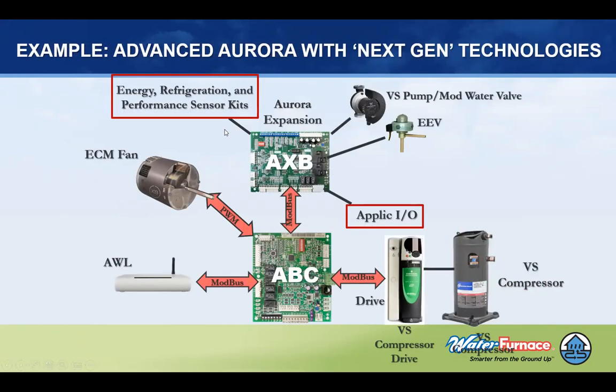When we add advanced controls onto the base controls, it can significantly increase the I/O that we can have from our system, the inputs and outputs, and adds significant capabilities such as variable speed compressors, electronic expansion valves, and variable speed pumps. But from a diagnostic standpoint, we add energy, refrigeration, and performance sensor kits to the system, significantly enhancing the knowledge of what we have working on our equipment.